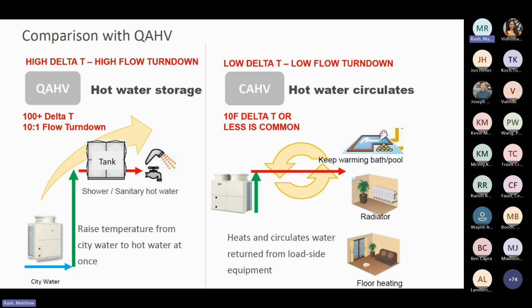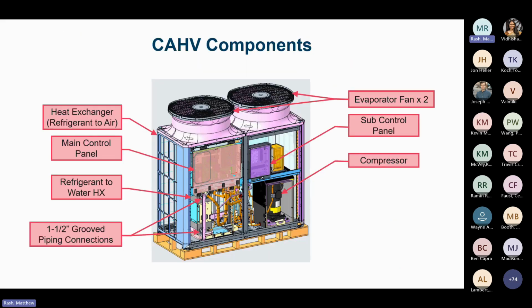It is A2L, obviously 454C, so low GWP, compliant with transition rules. So again, this is a single capacity lineup. It'll be available in 460 initially, and then shortly after, probably in April, March timeframe, there'll be a 208 version available. This system can be combined up to 16 modules, so nominal capacity up to over 2,000 MBH. It's reverse cycle hot gas defrost. The pressure rating for this is much higher than what you have on the QAHV unit, so up to 145 PSI. The QAHV unit does not have that. So this is an integral refrigerant to water brazed plate heat exchanger, so much more suitable for higher pressure applications on heating hot water systems in the commercial realm.